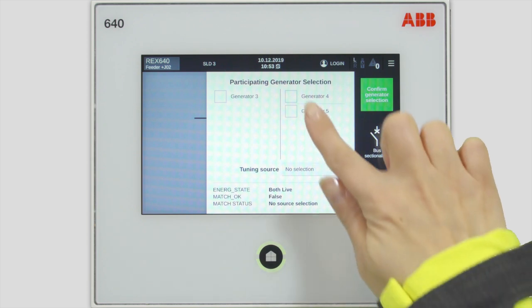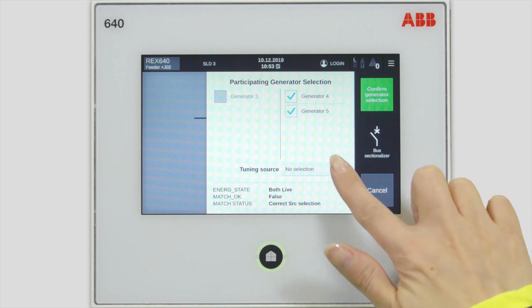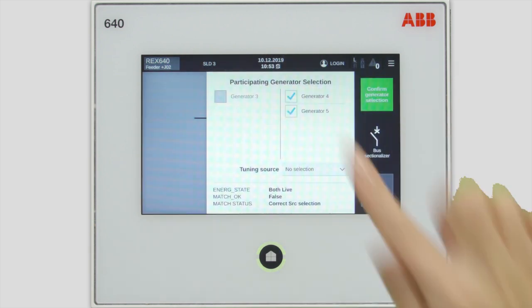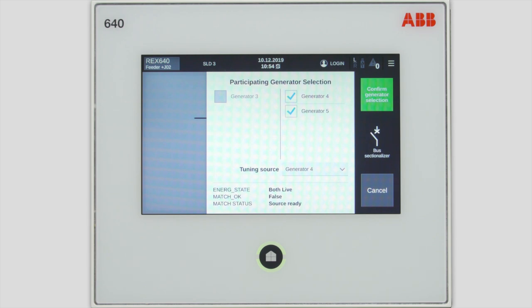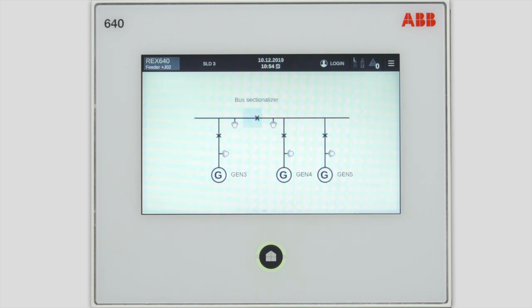Let's select generators 4 and 5. Notice that generator number 3 becomes unavailable since it's on the other side of the bus sectionalizer breaker. Additionally, you can select a fine tuning source, meaning that the selected generator 4 will be used for the fine matching at the very end of the synchronization process. Now you are ready to confirm the generator selection and proceed. Here you have a synchroscope view with measured frequency and voltage, but no controls since the relay will automatically control both the voltage and the frequency of the participating generators, and it will close the breaker at the suitable point in time.